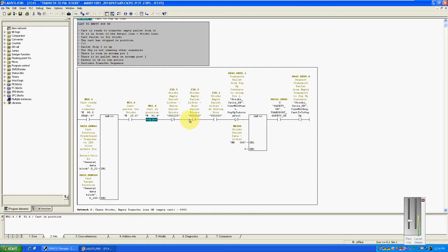And here are some pallet sensors on the cart, so I'll make sure that there is no pallet before the lifter and actually on the lifter, and I'll make sure that the lifter is down. The lifter has an airbag that pulls a smaller chain conveyor up, so that's got to be down to allow the transport of the pallet onto it. The bottom prox has got to be true, and I can't be running another sequence that involves these conveyors. The only other sequence that involves these conveyors is transferring from the pop-up conveyor to accumulator position one. So I can't be trying to drive to accumulator position one and then want to drive onto the pop-up as well.